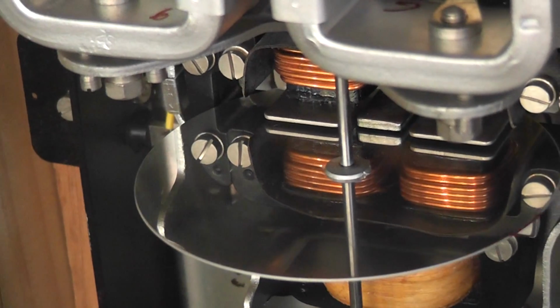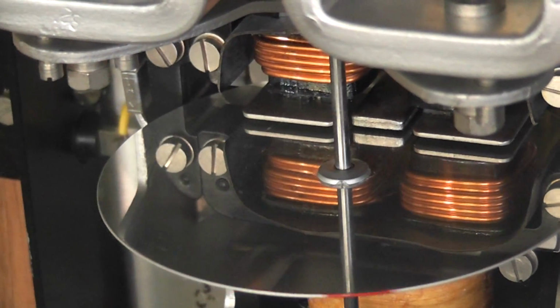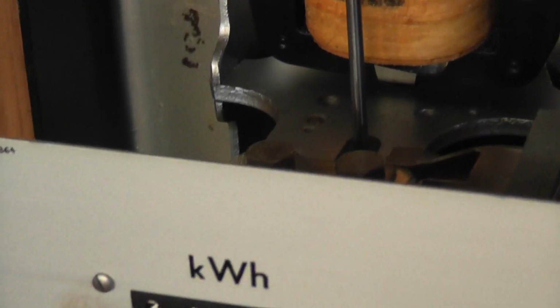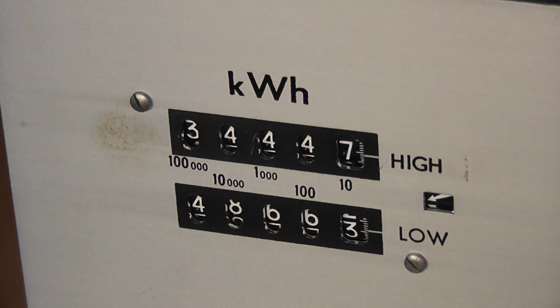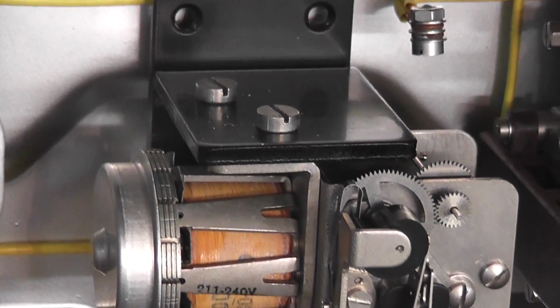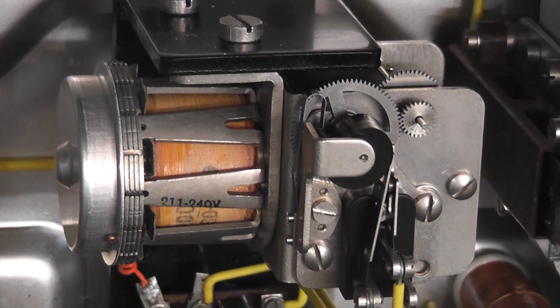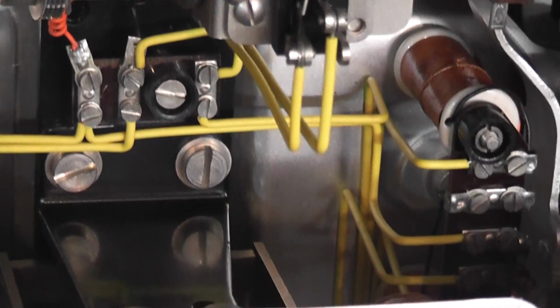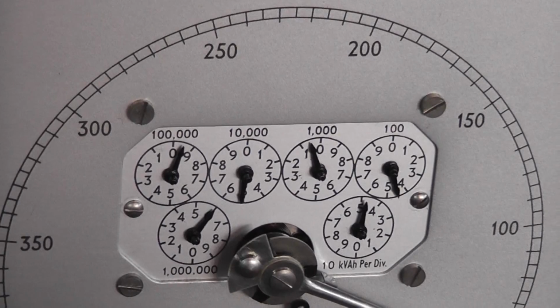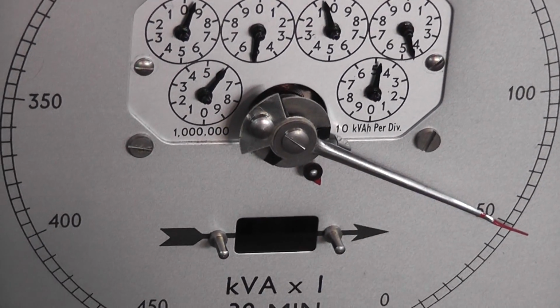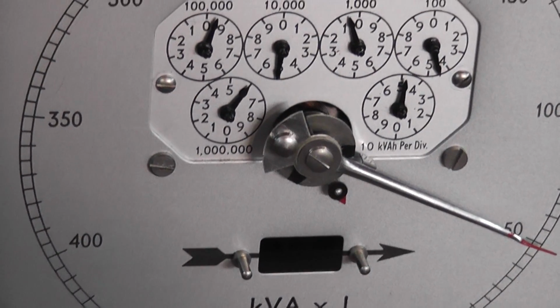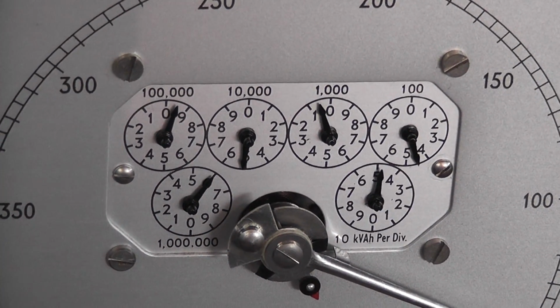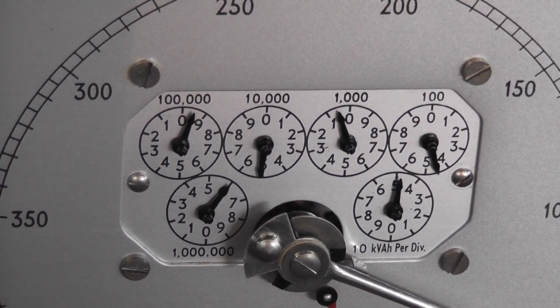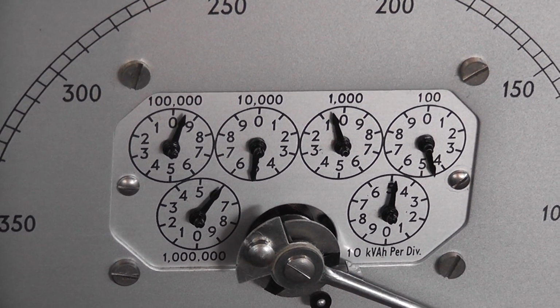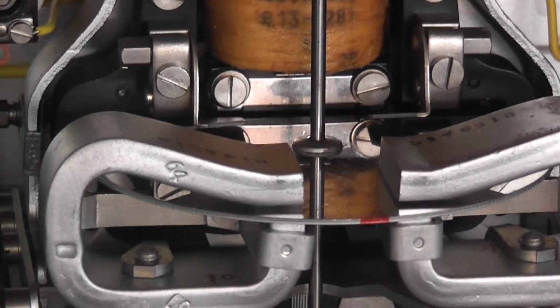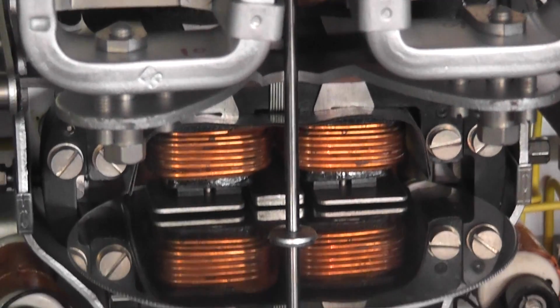Discs are almost like mirrors. If you look at this, it's just a perfect piece of engineering. Two rates, low and high rate. KVAR component is geared from both of the meters, and here we got a timing device which controls the maximum demand indicator. This is an integration period of 30 minutes and resets the dial every 30 minutes. KVA times 1. This meter, as I said before, reads for 500 to 5 ampere, and the highest reading is a million units or KVAs. And that's the KVAR register, which is not moving at this stage because of resistive load applied.